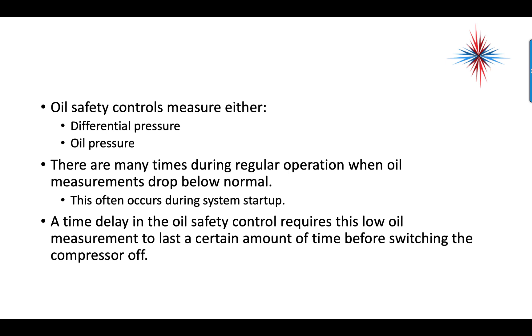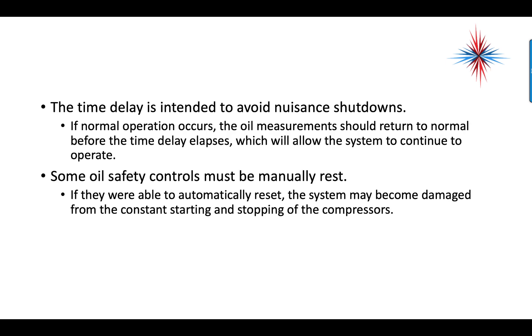Oil safety controls measure either differential pressure or oil pressure. There may be times during normal operation when oil measurements drop below normal — this often occurs during system startup. Usually a time delay in the oil safety control requires this low oil measurement to last a certain amount of time before switching the compressor off. If normal operation occurs, the oil measurements would return to normal before the time delay elapses, allowing the system to continue to operate.